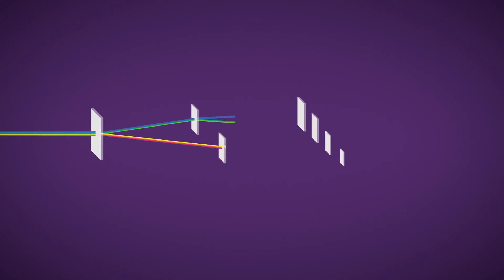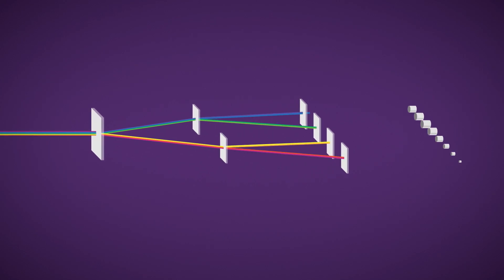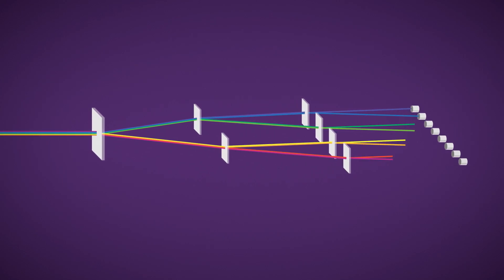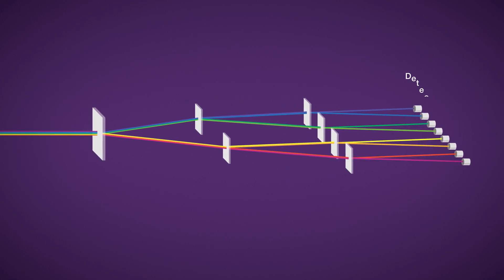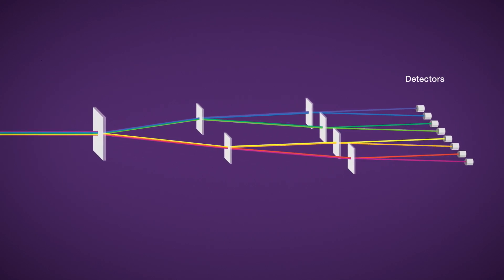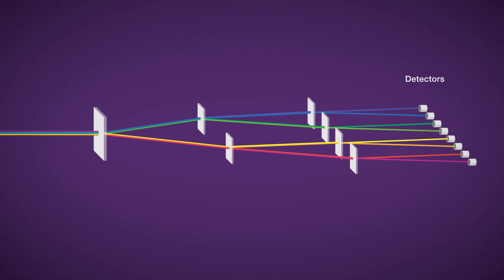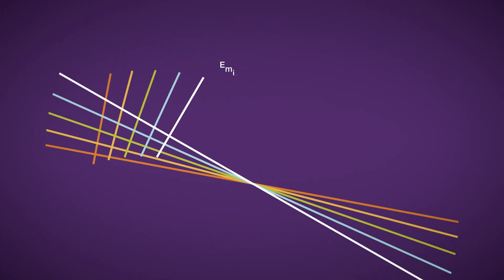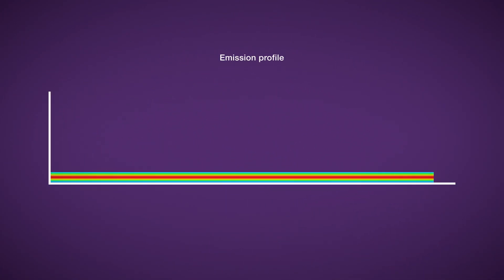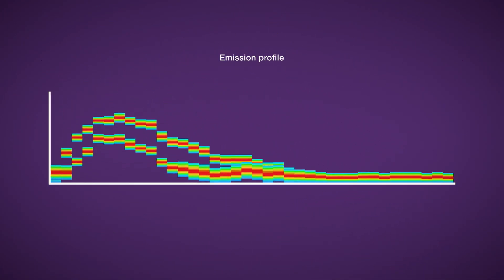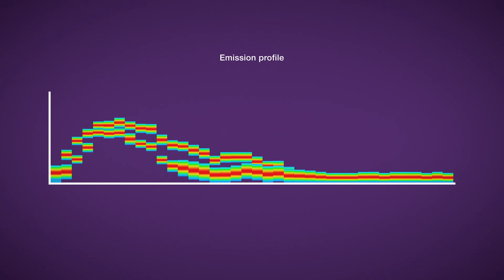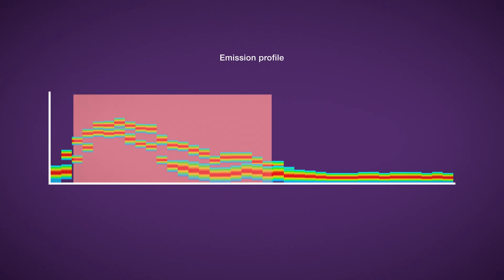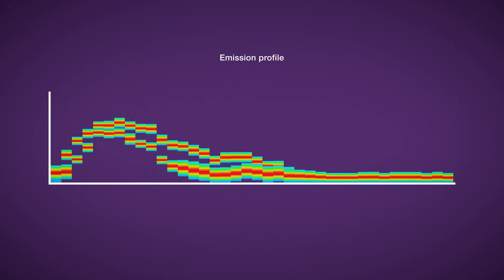When the fluorophores are excited by the lasers, the emitted light is captured across an array of detectors. A unique spectral signature for each fluorophore is generated by collecting the emission profile. Because all emitted photons are captured in the spectral signature, there is higher sensitivity to dim signals.